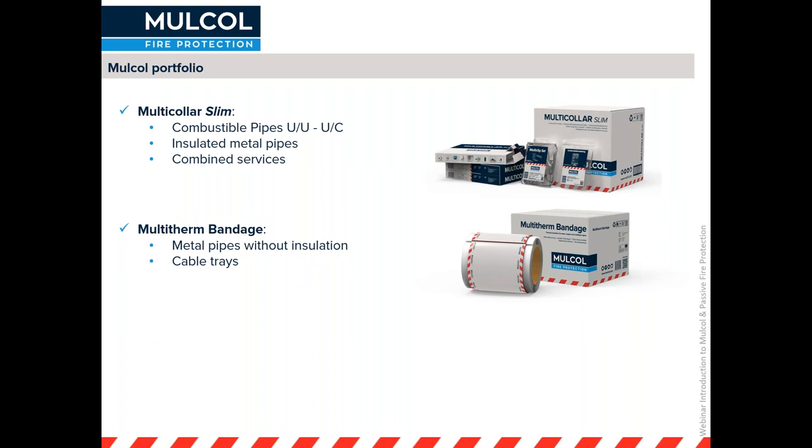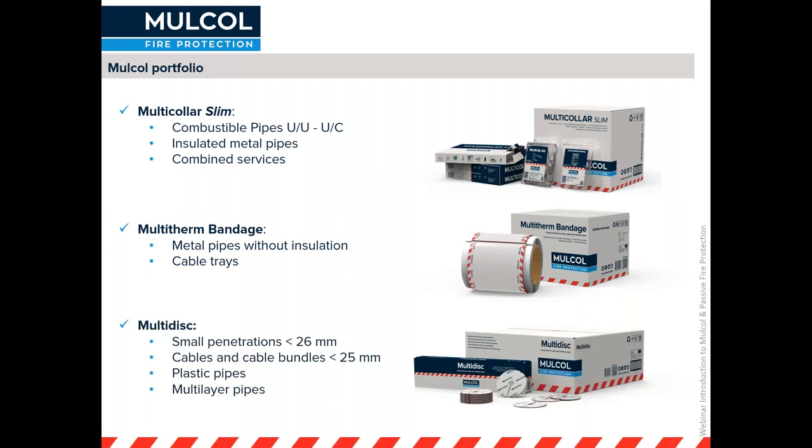The Multitherm Bandage, this is what I spoke about earlier, where you've got metal pipes without any insulation, transferring the heat really quickly, but you still need to achieve your thermal insulation of your fire stopping. So with the Multitherm Bandage, it absorbs the heat, and therefore you will be able to achieve the insulation rating of your criteria. We can also use them on cable trays, so they're mainly for metal pipes without any insulation.